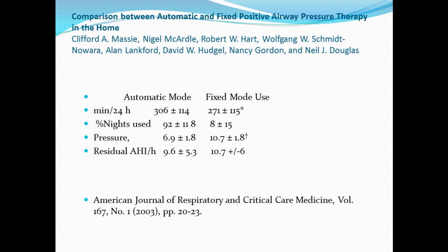What they do is the device looks at the uptake of airflow over time, and when the curve, which normally has a roughly curved shape like that, starts to square off or starts to accelerate more slowly, the pressure is increased automatically. Some people have an arousal during that period of time and don't tolerate it because they end up having arousals even though they don't have frank obstructions. Now, this is an old study, but there have been plenty since then that show that if you use the automatic mode, the compliance rates, the number of hours you use a night, is about the same. The pressure is typically a little lower, and the residual amount of sleep apnea is about the same. So the literature says that the automatic mode is about the same as having somebody on a fixed mode.